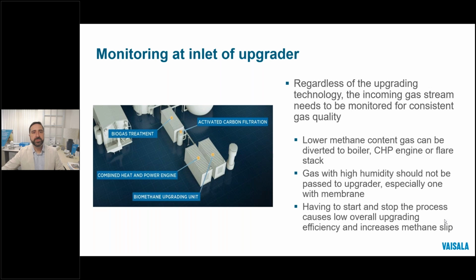This one is fairly intuitive as well, since you need to know the gas quality before sending it to the upgrader. The methane concentration, along with the pressure and flow rate, will determine the potential volume output that you can expect, allowing for adjustments to the system to ensure efficiency and uptime. This can also help predict the tail gas volume, and I'll touch more on that measurement as well. If the gas is found to be of low quality, it can be diverted to different uses, such as feeding the boiler, the CHP engine, or sent to the flare in the worst case scenario.